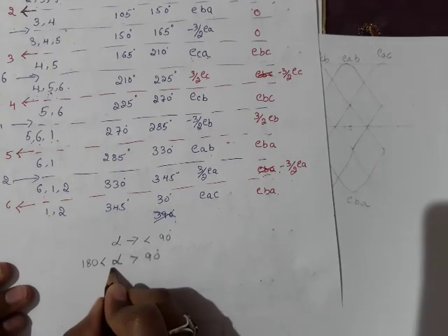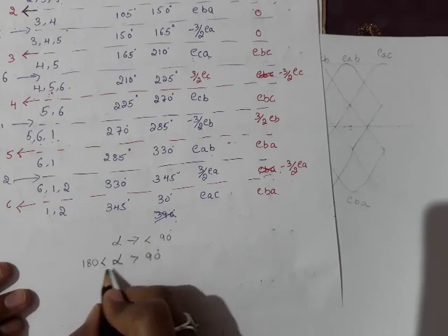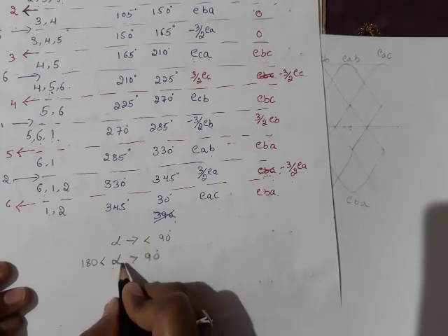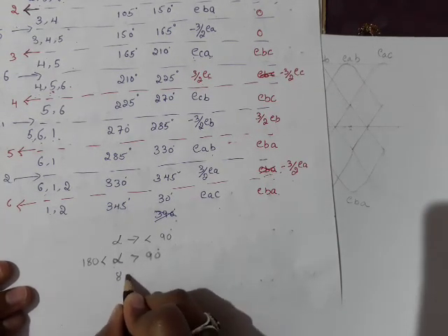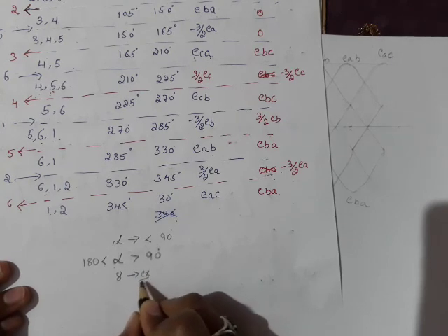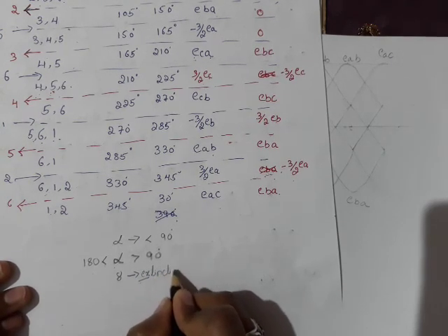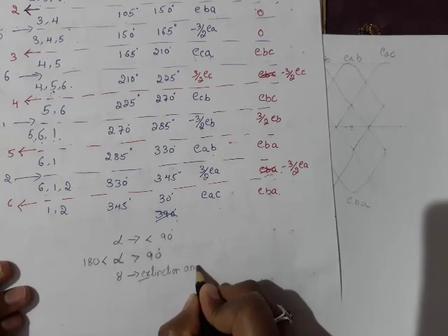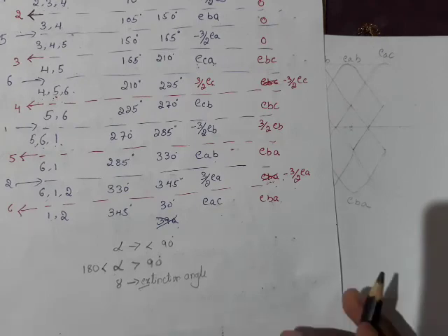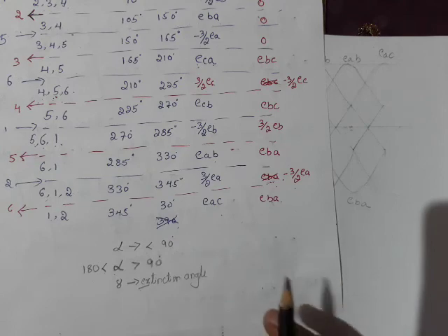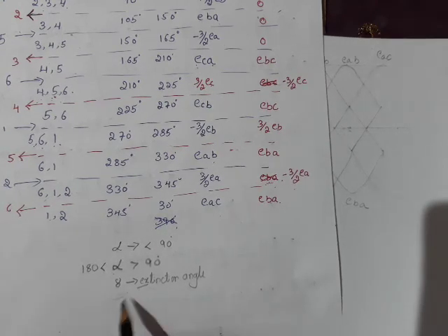But even though it should be less than 180 degree, we cannot trigger it at 179 like that. We have to give some delay angle. That delay angle is called gamma, the extinction angle. I told you why we need to leave this extinction angle: we have a problem of overlap angle. If the overlap angle exceeds some value, valve number 3 will not come into conduction, rather valve number 1 will continue to conduct. To avoid that problem, we should leave some angle, that is the extinction angle.